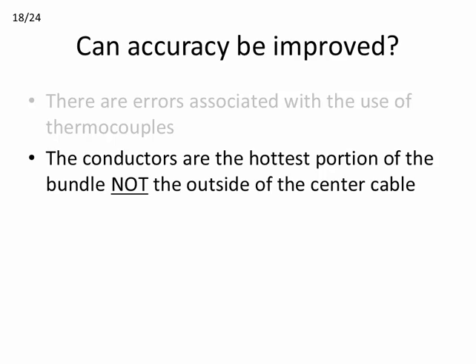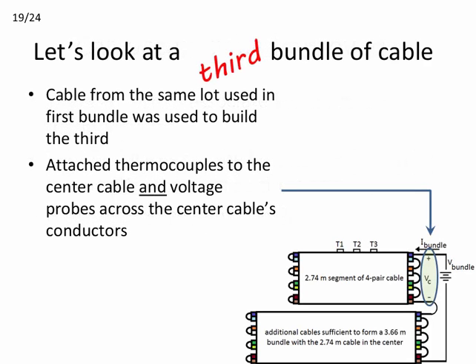But there are those that don't trust the data obtained using thermocouples. They'll point out, rightfully so, that it's the conductors in and not the jacket outside of the center cable that are the hottest portion of the bundle. To ensure that the thermocouple data is correct, we need a way to determine the temperature of the conductors and to determine if there is a significant difference between the conductor temperature and that recorded using the thermocouple method.